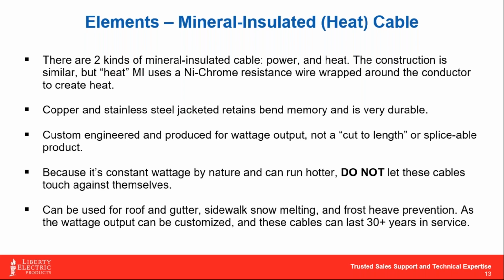The big downside to this cable is that it behaves like a constant wattage cable - you cannot let it touch against itself or it will burn through. The other part is that this is not a field serviceable cable, so the measurements have to be exact. These products are actually built to length, so depending on the application and how much heat output is needed, this product will be engineered and built to a specific purpose.